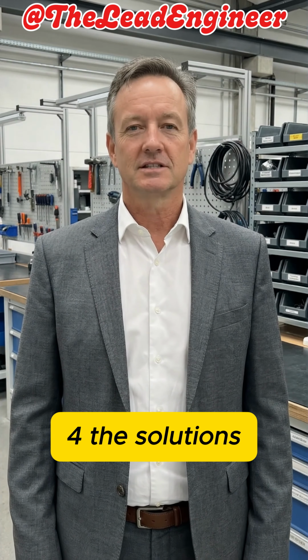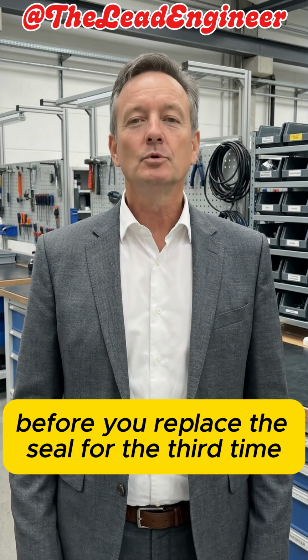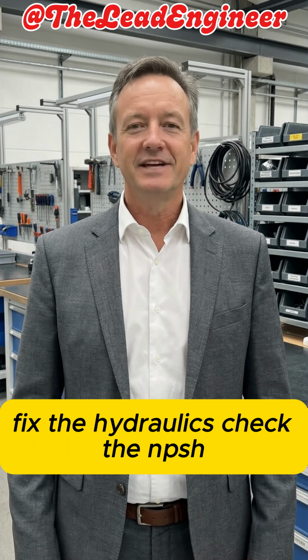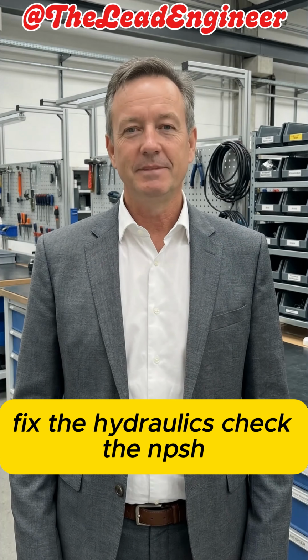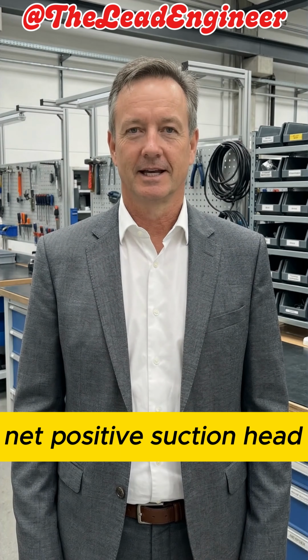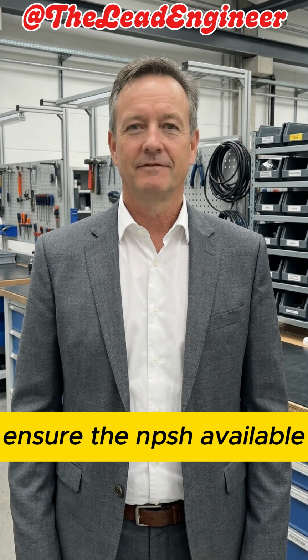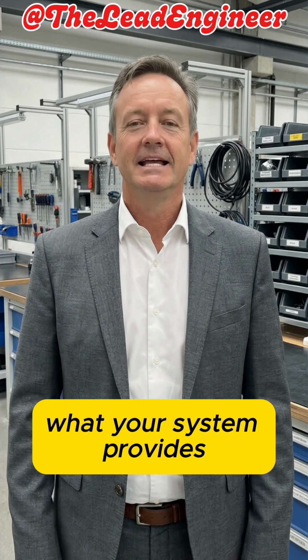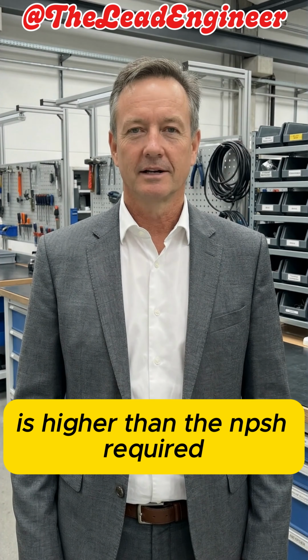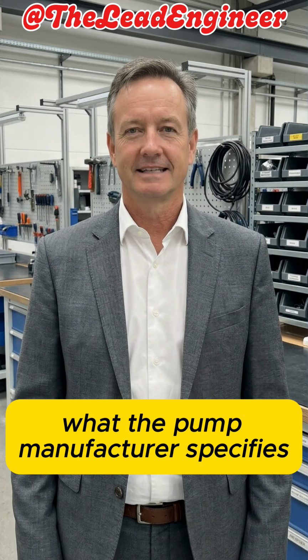4. The solutions. How to fix it. Before you replace the seal for the third time, fix the hydraulics. Check the NPSH, net positive suction head. Ensure the NPSH available, what your system provides, is higher than the NPSH required, what the pump manufacturer specifies.